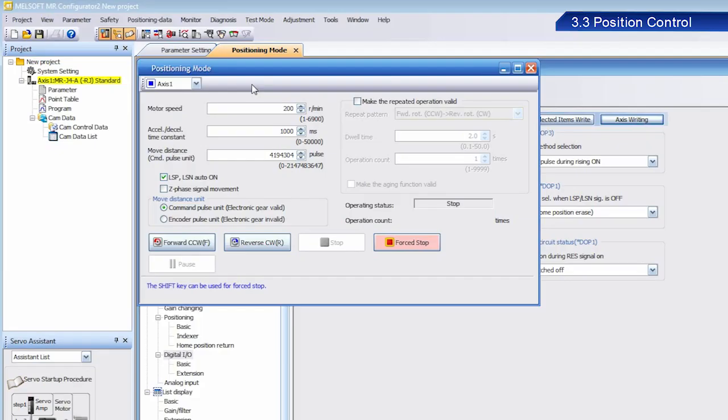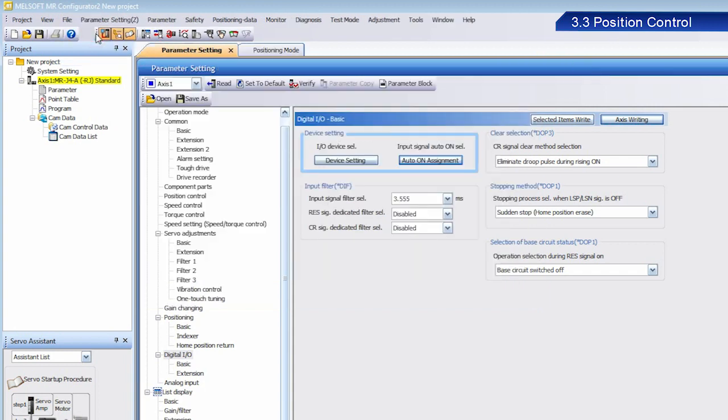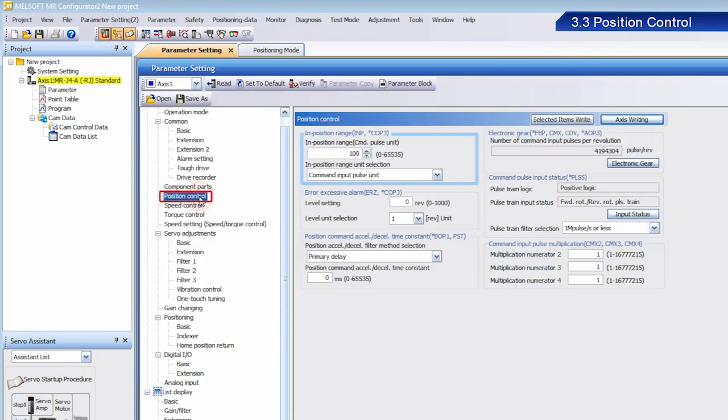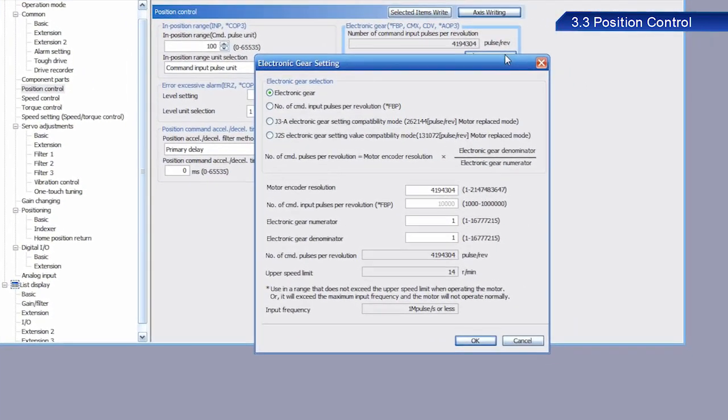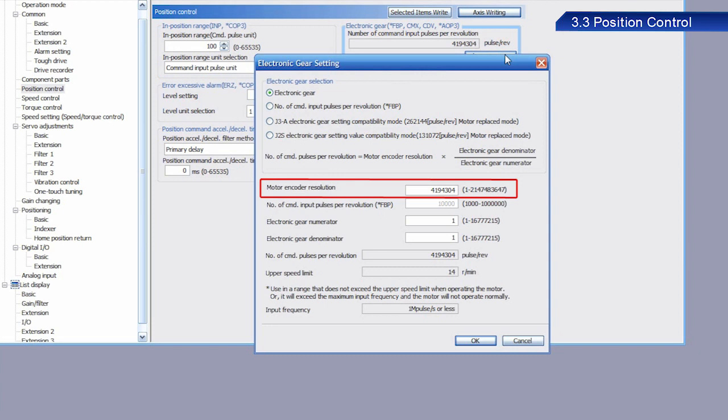Next, let's set the electronic gear. From Parameter, select Parameter Setting, and then select Position Control. Click the Electronic Gear button. The Electronic Gear Setting dialog box appears. Find the Motor Encoder Resolution setting.